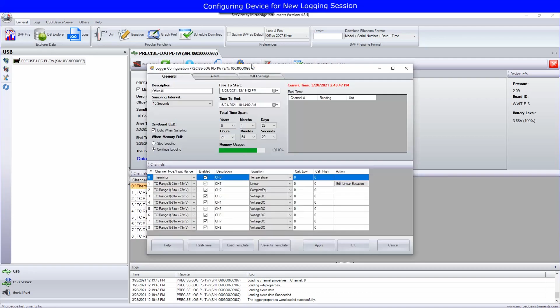Configuring device for a new logging session. If you decide to start a new logging session, the onboard flash drive memory will be reset. Please always download the data for your existing session before configuring it for a new session. Click Configure to show the configuration dialog. You may change the description, sampling interval, time to start logging, and when to stop logging. You may also change the channel settings such as description, enabling logging, equation, and calibration data, etc.